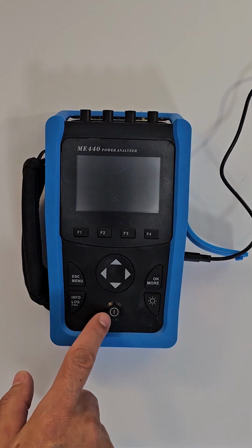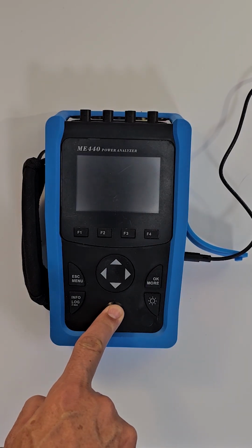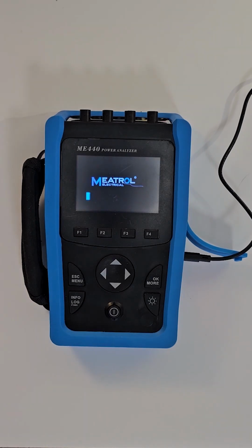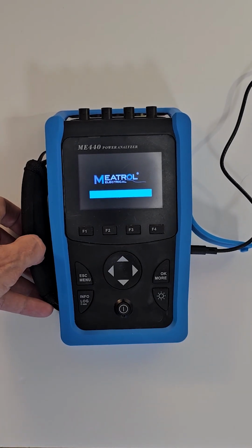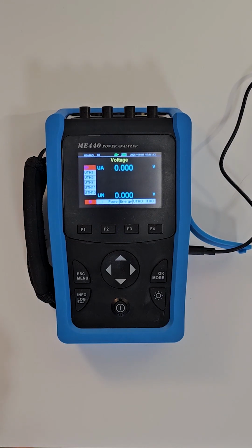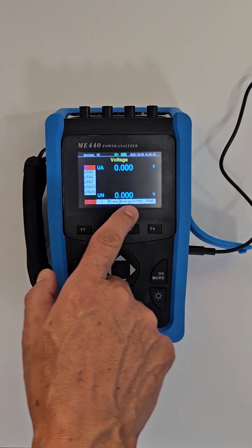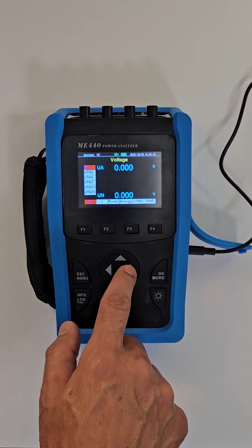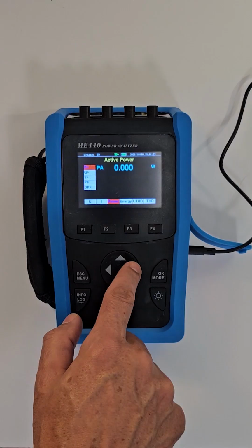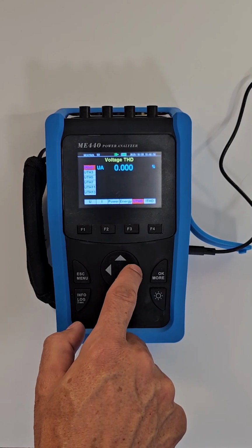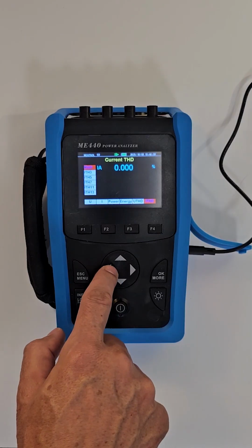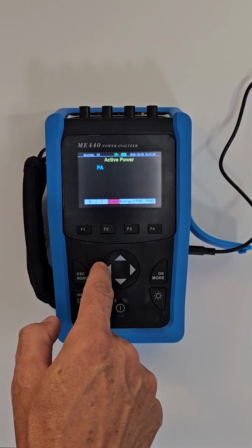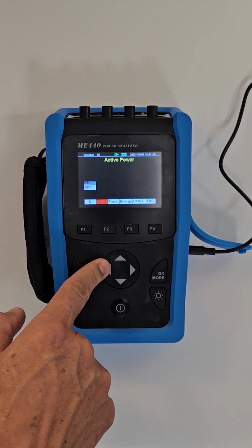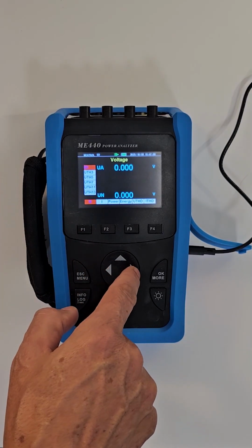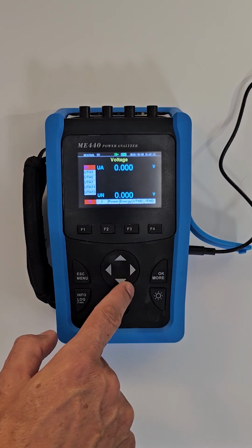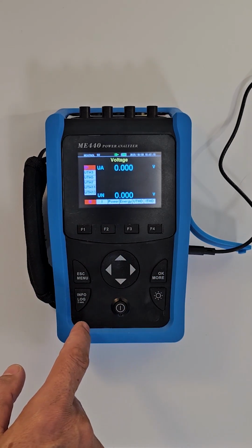Okay, so to turn it on, just press the power button for 5 seconds and then it will turn on. Okay, great. So we're on the home screen. Here you can see all the different factors that are being measured. First screen is voltage, then current, then power, energy, voltage total harmonic distortion, current total harmonic distortion. So at the moment it's set to single phase, so that's why it's only showing the first phase. We'll see now how to change it to 3 phase.